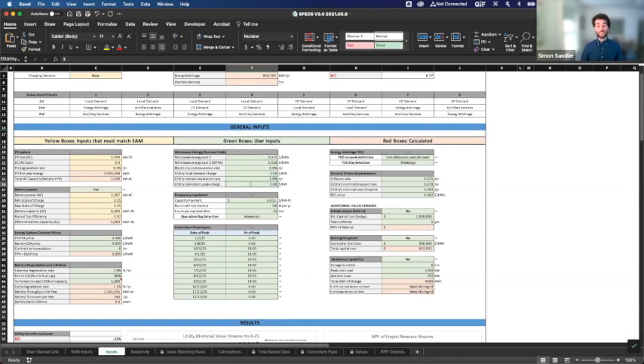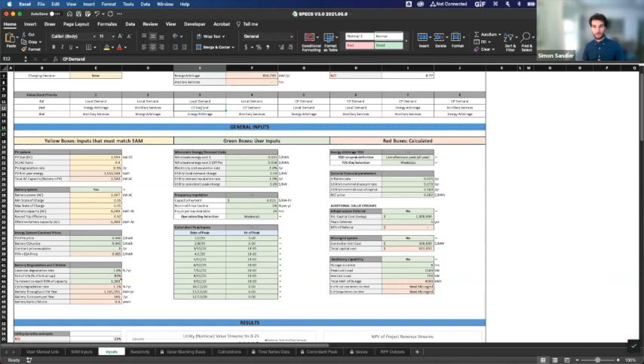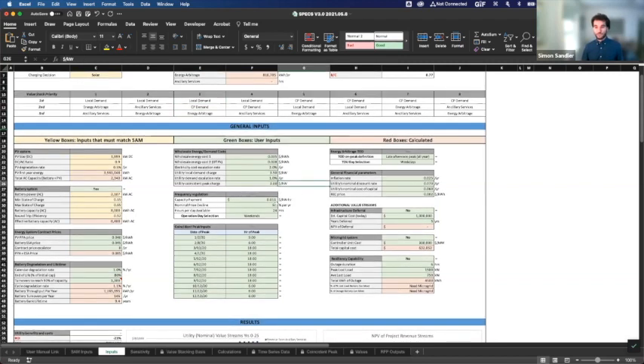The utility coincident peak demand charge is the charge based on what hour the G&T sees its system-wide peak — you get charged at the end of the month based on your consumption during that hour. Here it's three dollars per kilowatt during that hour. That's why we selected coincident peak as the second value in our value stack — we didn't choose it first because it costs a little less to the utility when purchasing power. We also have frequency regulation, but it shows 'no' since the value stack we're using doesn't account for it.